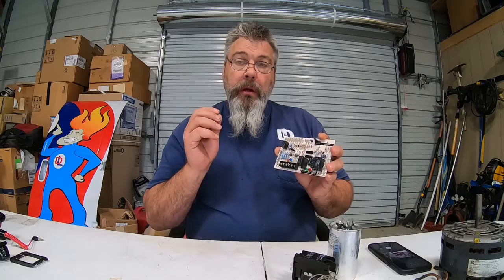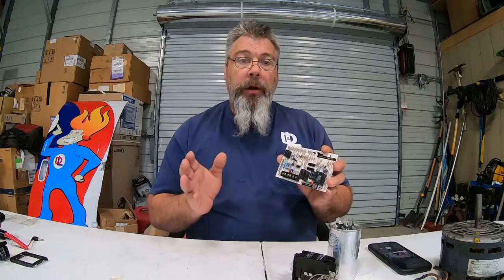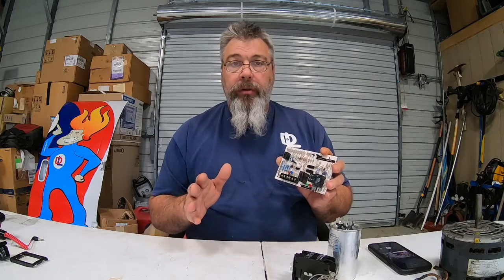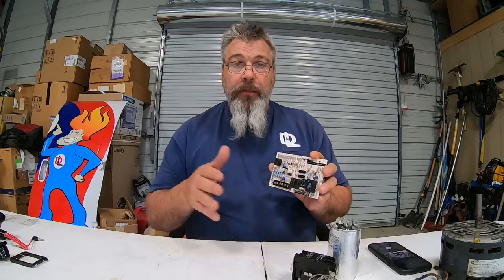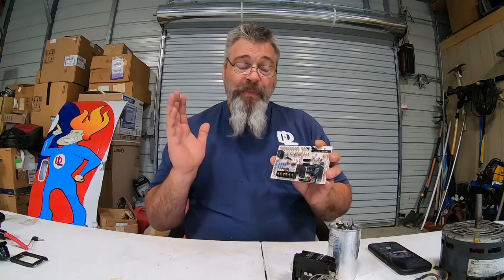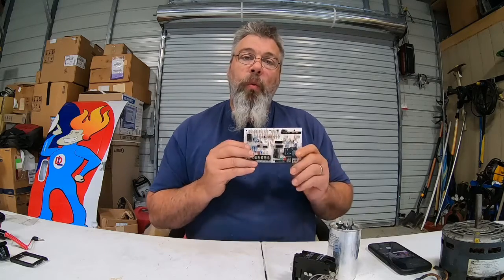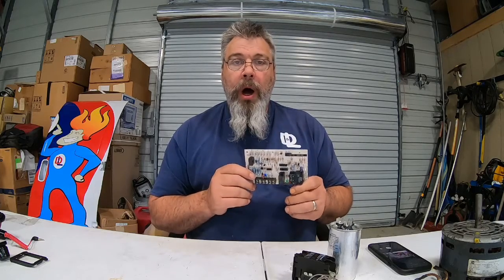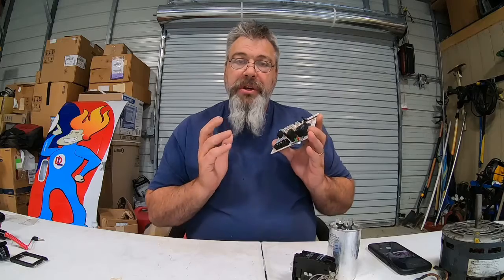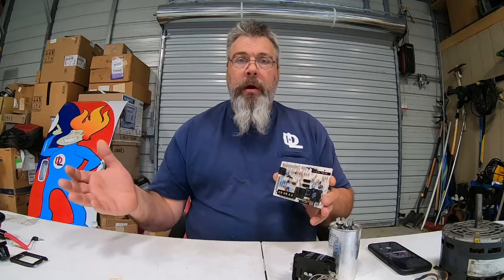I'm going to talk a little bit about defrost, because it's important to understand that heat pumps were not designed to run below 35 degrees, okay? They're not efficient anymore. We'll talk about efficiency and SEER rating and all that other stuff, but they're not efficient when the temperature outside gets below freezing. And why? Because in heating mode, we are taking the heat away from the outdoor air.